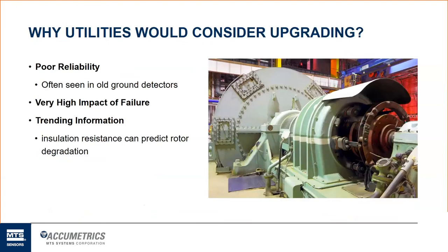So what a lot of utilities will do in that case is schedule sort of unnecessary outages just to check and make sure they don't have a ground fault and turn the unit off. And when you're off, not creating energy, you're losing money. And that's something that they don't like. So our trending information and our ability to more accurately measure the field resistance gives them that peace of mind that they're going to be monitored much more accurately than traditional systems that are out there.